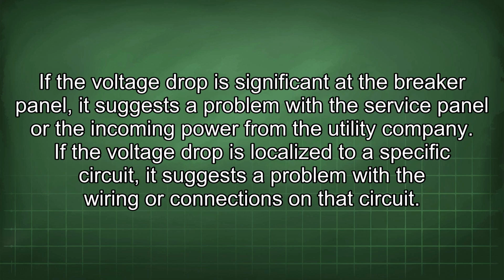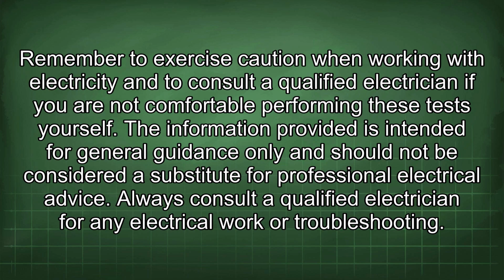If the voltage drop is significant at the breaker panel, it suggests a problem with the service panel or the incoming power from the utility company. If the voltage drop is localized to a specific circuit, it suggests a problem with the wiring or connections on that circuit. Remember to exercise caution when working with electricity and to consult a qualified electrician if you are not comfortable performing these tests yourself.